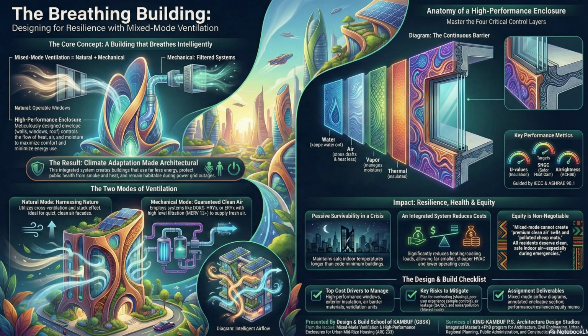Yeah. And the simplest but maybe most critical control is the window sensor or interlock. To stop people from running the AC with the window open. It prevents the ultimate waste. Running the air conditioning or the heating while a window is wide open. If the window opens, the system in that zone has to immediately pause its conditioning cycle. It seems so basic. It's basic logic, but you'd be amazed how often it's value engineered out of a project, leading to massive energy hemorrhages.